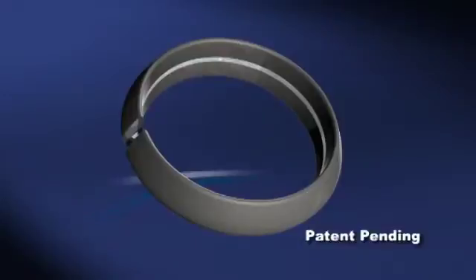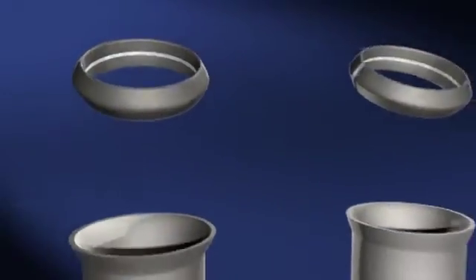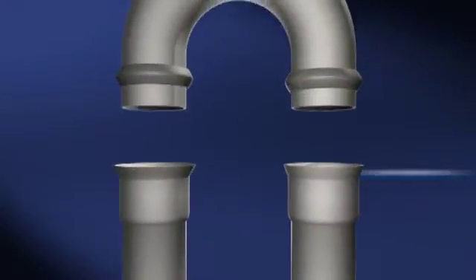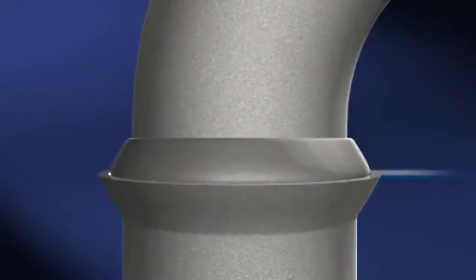Lucas Milhaupt has the solution. Our engineers have pioneered a new triangular-shaped brazing ring for the air conditioning market that seats in the hairpin and directs material flow for a cleaner, stronger joint with little to no overflow.